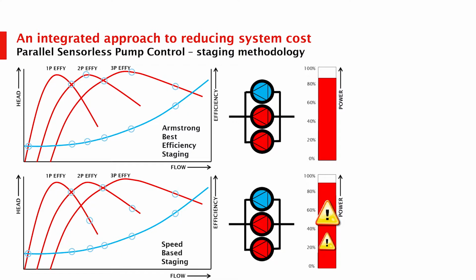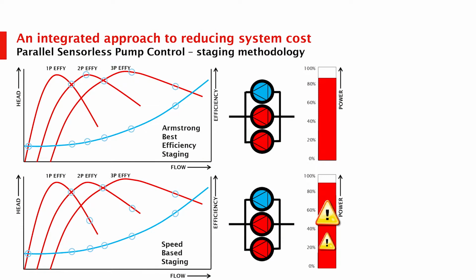In the second situation, on the bottom, it will run that pump, or chiller, or whatever it is, right up to maximum capacity, way past its peak efficiency. Anything designed for part load will be more efficient at a part load operating point than at full speed. So the way we recommend sequencing is that, based on the marginal efficiency of the particular piece of equipment, a second piece of equipment will come on and keep them as close as possible to their optimal efficiency. So 2 pumps versus 1 pump on the bottom. Same thing happens. This little caution sign is for the next slide, to indicate the biggest difference in efficiencies.